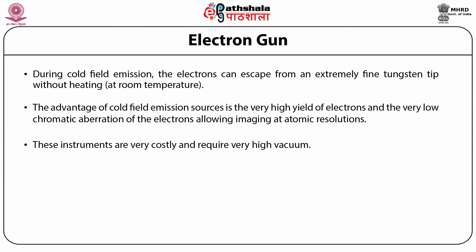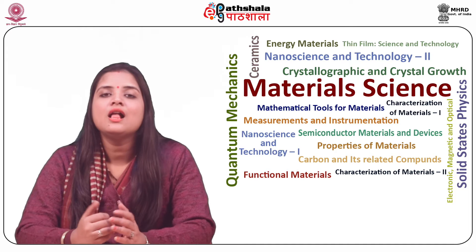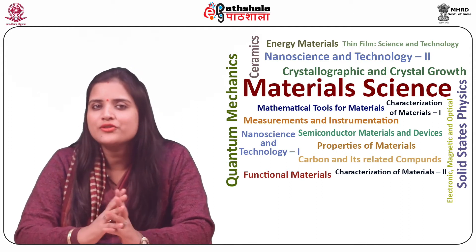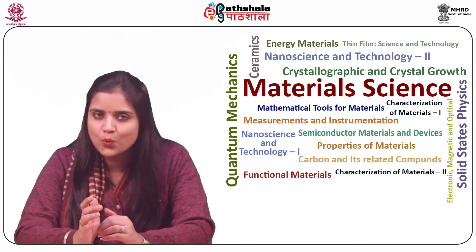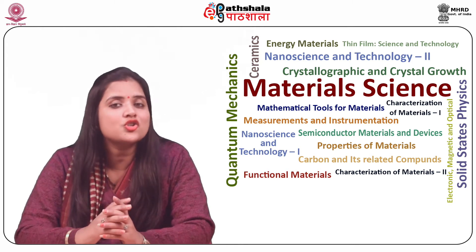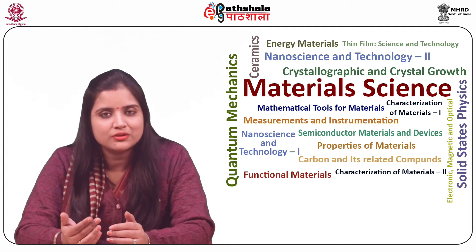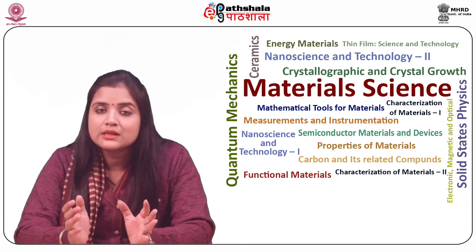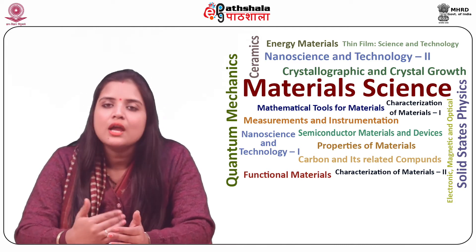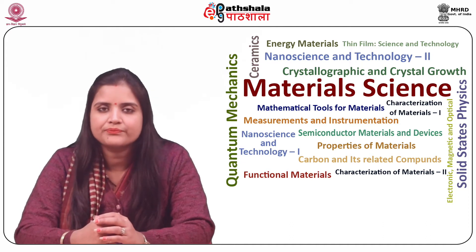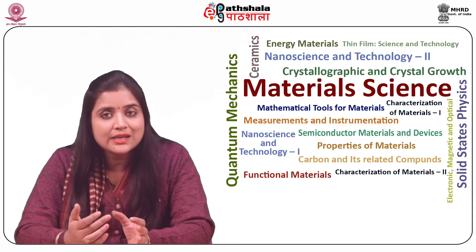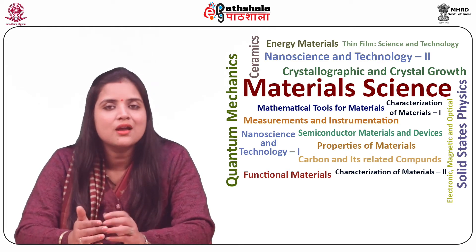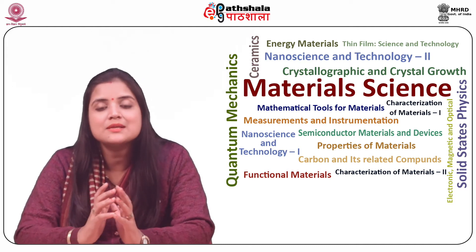The working of the electron gun can be controlled based on three parameters: the first is the accelerating voltage; the second is the current of the filament and therefore its temperature; and the third is the Wehnelt cap or bias voltage. The temperature of the filament tip is controlled by the filament current, which in turn controls the amount of emitted electrons. The filament current is increased until the number of emitted electrons no longer increases, meaning the filament is saturated, in order to maximize emission.